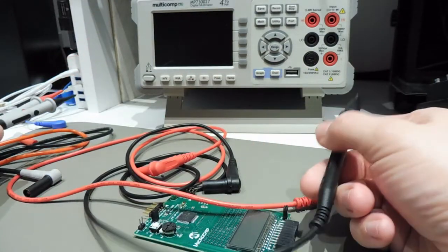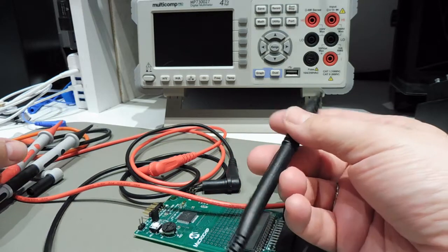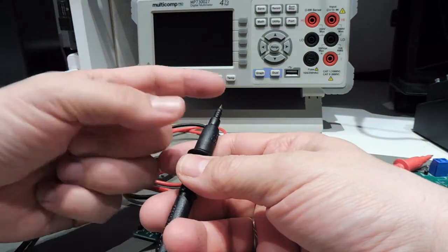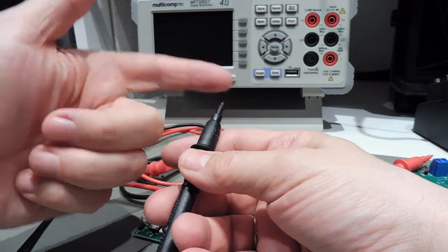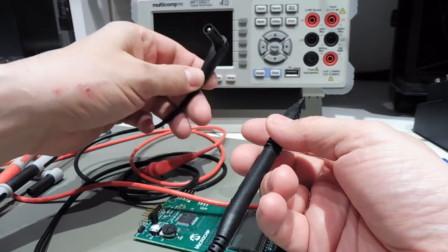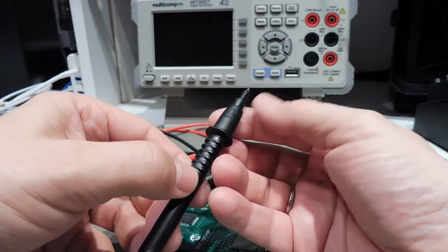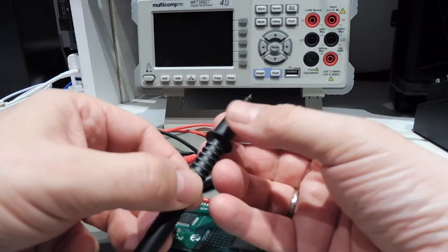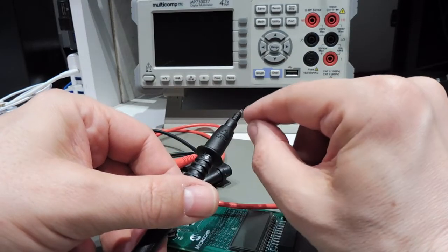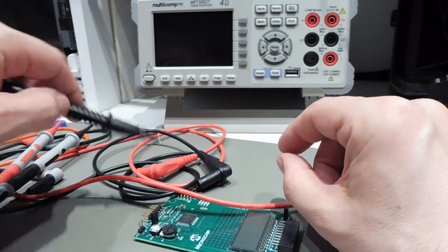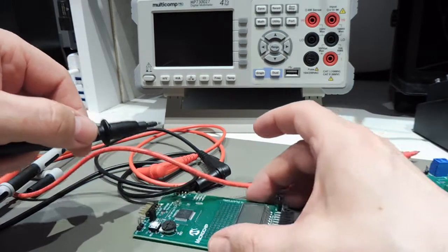The last thing to look at is total resistance, meaning the resistance from the tip of the probe to these connectors. That's important for several reasons: if the resistance of the tip is too high, you probably don't get good contact, and you might measure wrong values, especially for resistance but also for other types.